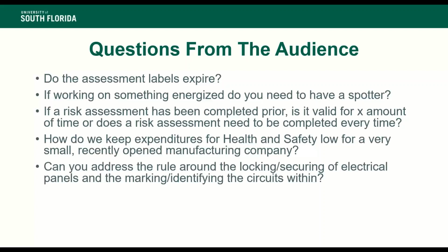Thank you, Dr. Ward. Our next question, a request. Can you address the rule around locking and securing of electrical panels and the marking and identifying of the circuits within? I'll take that one. I'd like to address the second part first. Marking and identifying the circuits within electrical panels really is a requirement. OSHA requires it, as well as NEC, the National Electrical Code. Locking and securing of electrical panels has become somewhat controversial, especially with OSHA's requirement that electrical panels be accessible. The National Electrical Code definition of accessible means not behind locked doors. So from that standpoint, electrical panels must remain unlocked to be accessible.